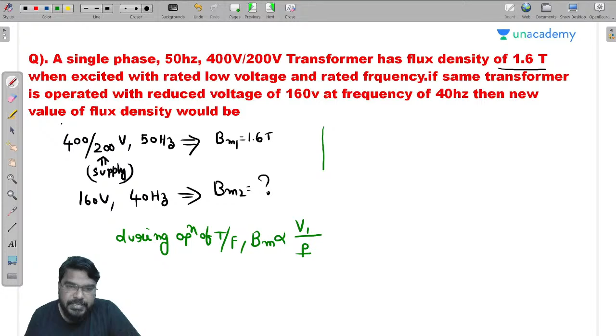During operation of the transformer, maximum flux density is directly proportional to the V1 by F ratio. So Bmax2 equals Bmax1 multiplied by V12 divided by V11, into F1 by F2. Since it's directly proportional to voltage, it's the second case divided by the first case; since inversely proportional to frequency, it's the first case divided by the second case.